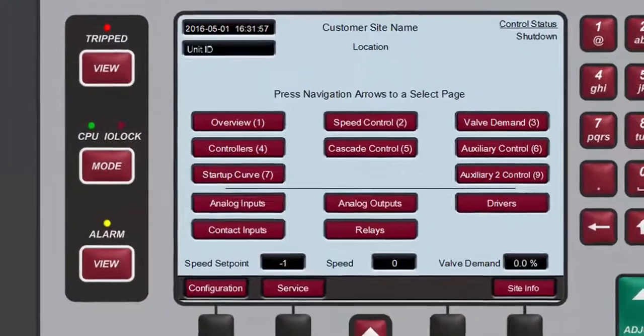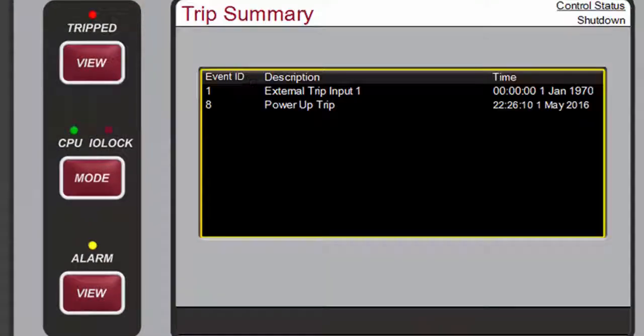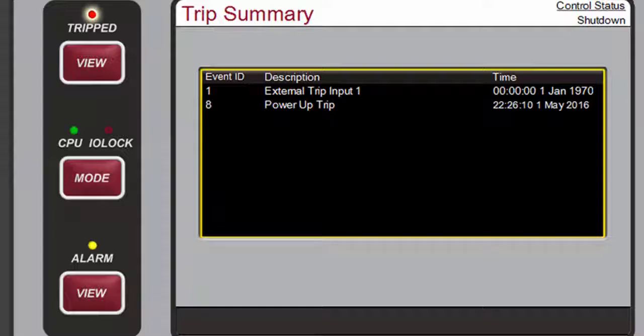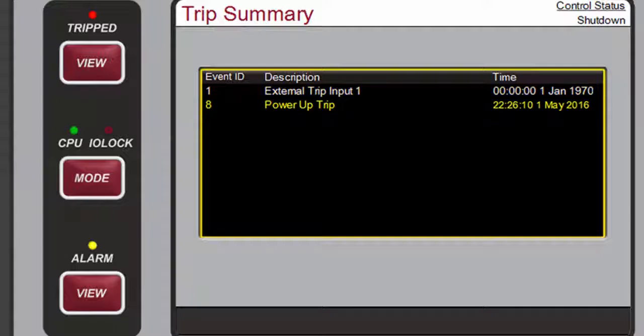Let's cover each of these buttons. Pressing Tripped View opens the Trip Summary screen. When a Trip is detected, it gets latched in the Event logic. The Trip Relay is de-energized. All Steam Valve demand outputs go to zero, and the Tripped LED illuminates red. The cause of the event will be indicated with an Event ID, Description, and Time and Date stamp. The list will always place the first Trip condition to occur at the top of the list. The most recent Trip condition to occur will always be placed at the bottom of the list.